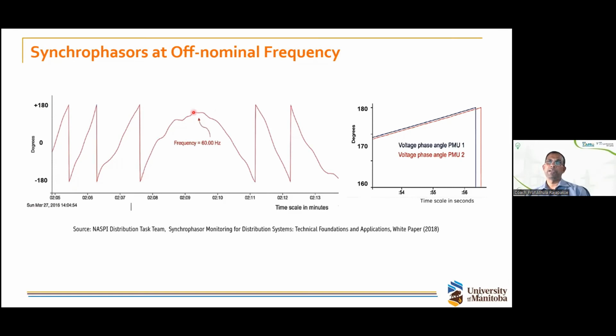So if you take somewhere like this one, here the phase angle remains almost constant, and that is because the signal frequency becomes equal to the nominal value. So when it crosses the nominal value, whatever phase angle you start observing will remain constant. And of course, if you start decreasing now, it changes in some other way, right? So this is something important that you have to remember. Also, if you are comparing the phase angle difference between two signals, because of these changes, a phase difference which may be very small could suddenly appear as a really large difference. That is not something wrong; it is because we are changing the reference for the phase angle reporting. So these are some normal things that you will observe.